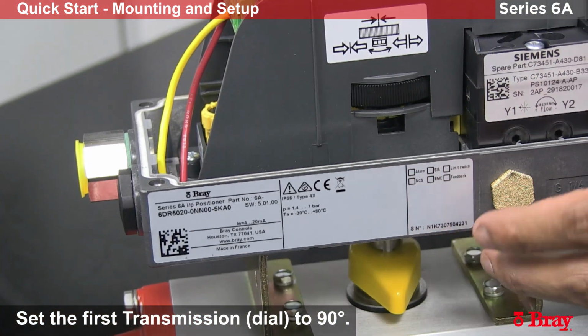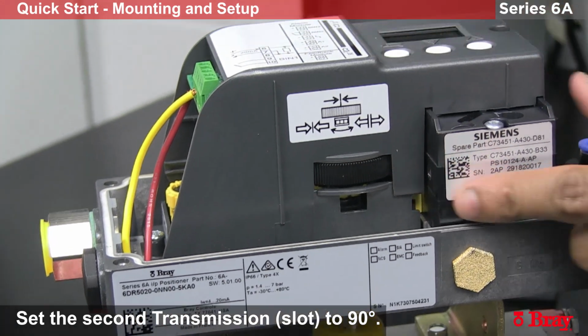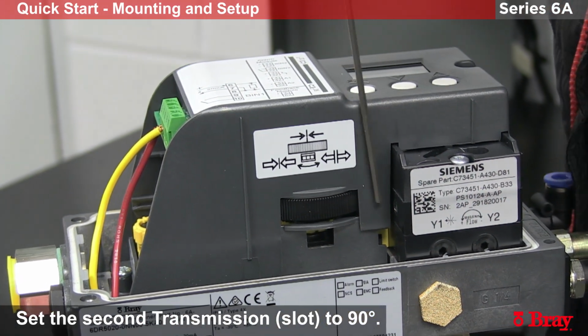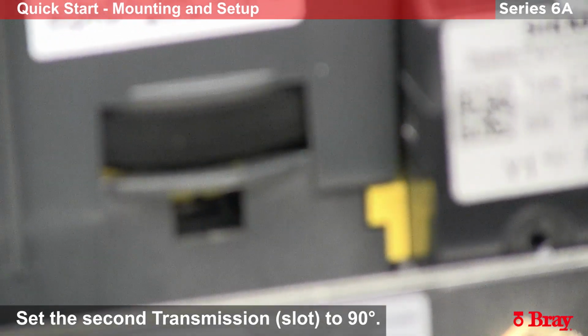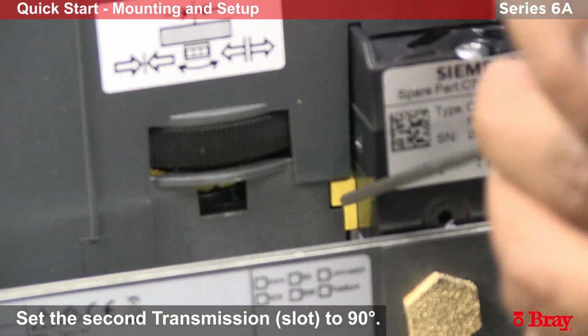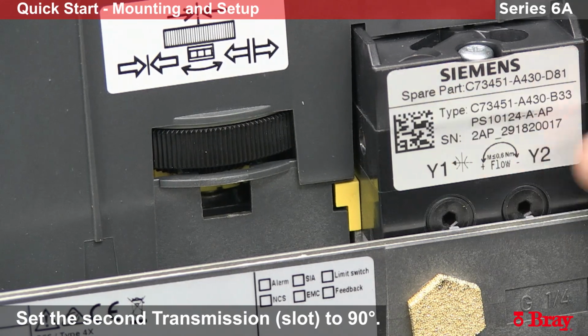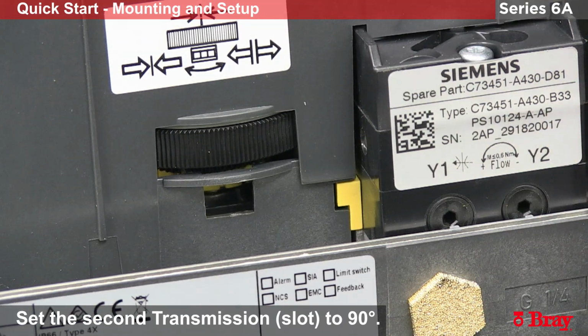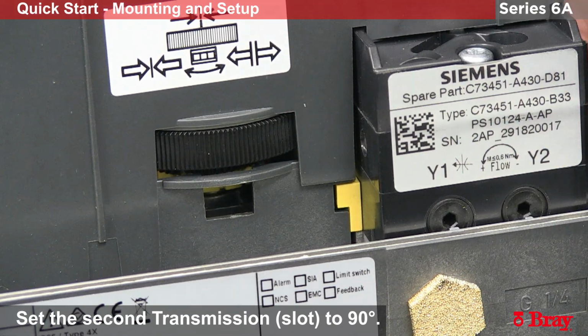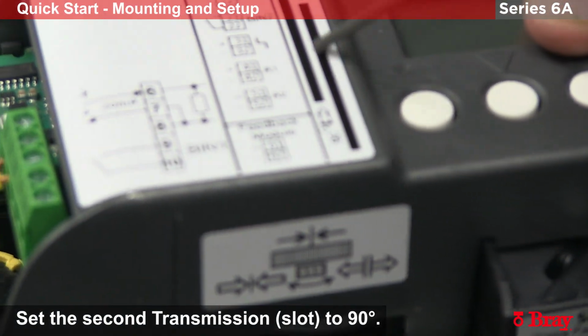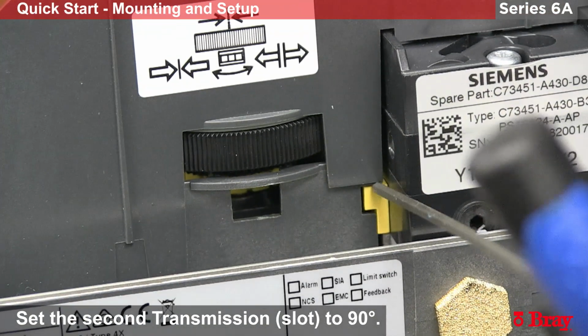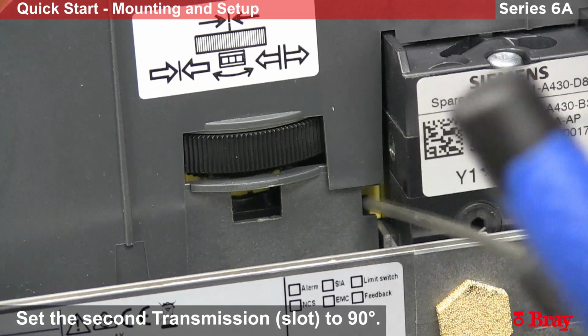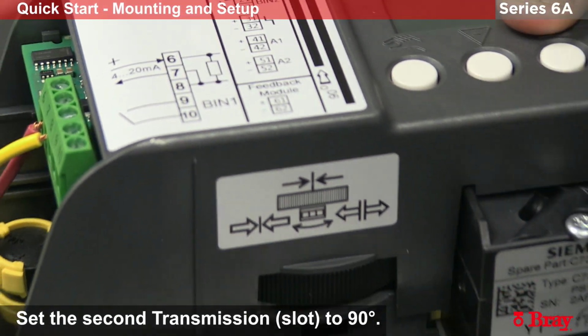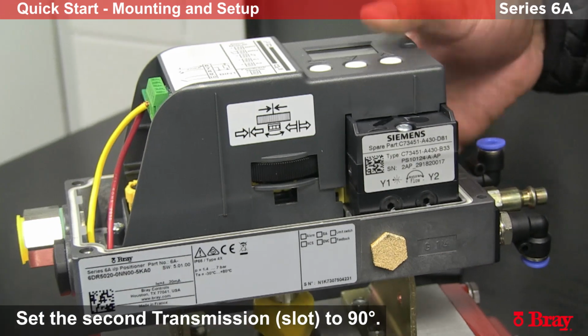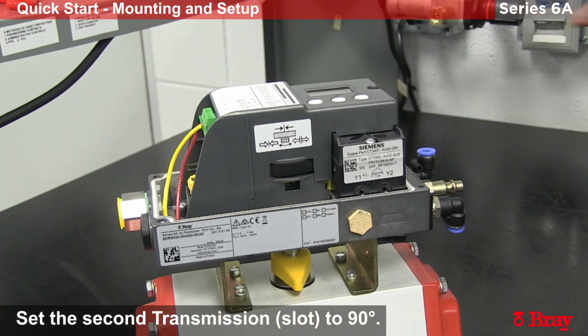The second transmission is located in this slot right here. There are 2 settings. In this setting, where you can see the yellow from the front, where you have the labels, this is set for 33 degrees of travel, as stated by the graphic up here. To set for 90, we will push it forward, indicating 90 degrees of travel. That completes the mechanical setup for the 6A positioner.